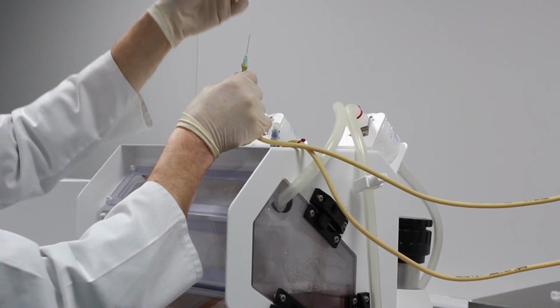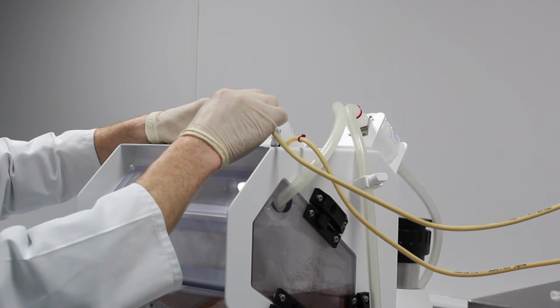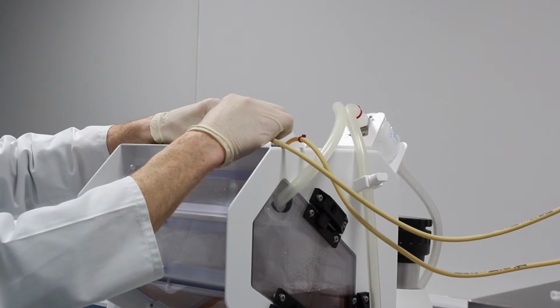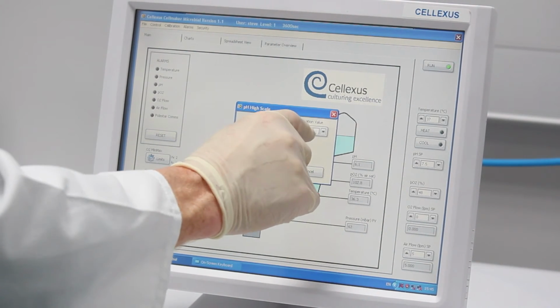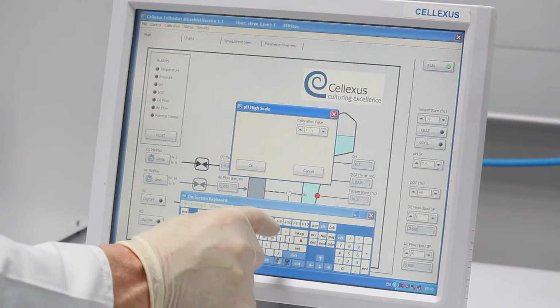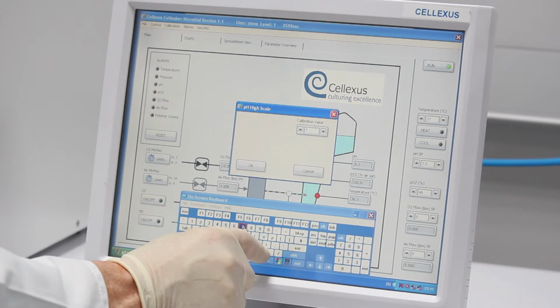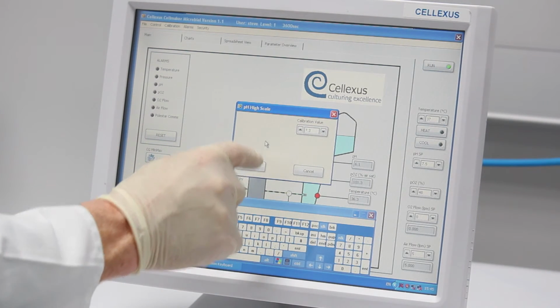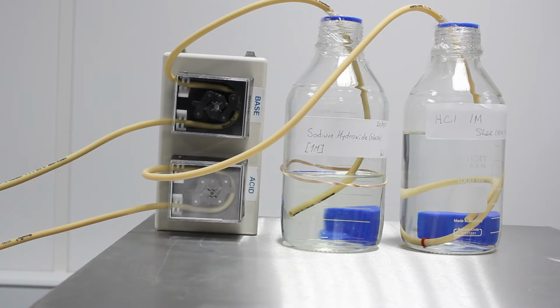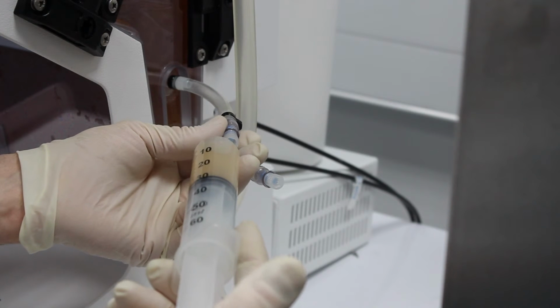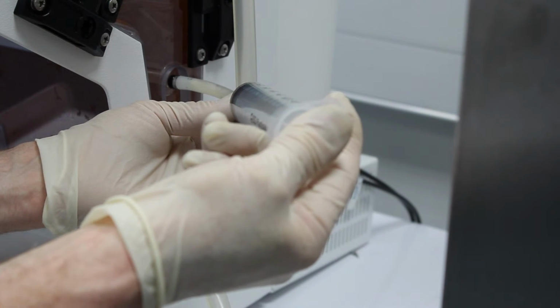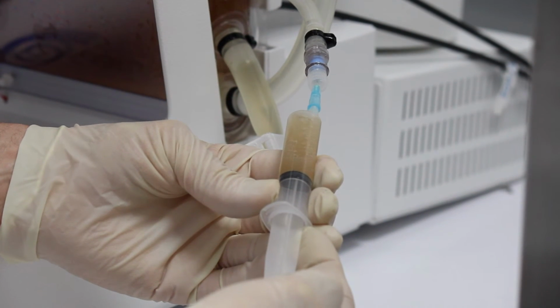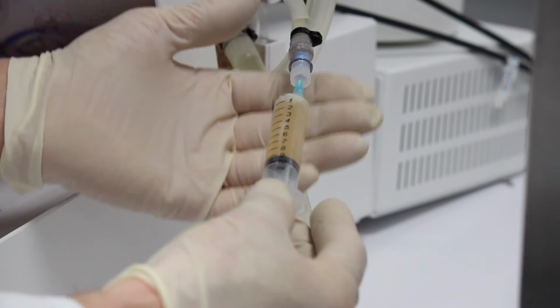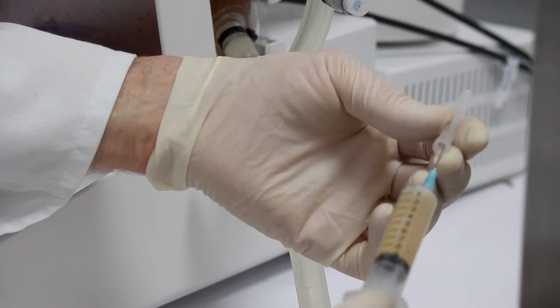Three inlet ports can be found at the top of the Cellmaker bags, which enable addition of acid and base to control pH, as well as addition of anti-foaming agent and glucose should that be required. On the Cellmaker Plus, a pH calibration step is performed, and acid and base addition is automatically controlled via monitoring the pH using the integrated pH sensor in the Cellmaker Plus bag and automatically delivering acid and base via a peristaltic pump as required. The inoculant is added via a sample port at the right hand side of the Cellmaker bag. The sample ports can also be used to enable samples to be taken or to allow addition of reagents to the media during the culture process.